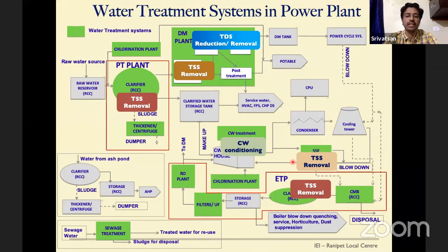Whatever waste is collected in the thermal power plant comes back to the effluent treatment plant, where first it is neutralized, then suspended solids are removed stage-wise. Then there is a TDS reduction. Then this water is reused back in the cooling water cycle. Whatever waste from this thermal power plant remains basically has to be solid waste. You cannot dispose of liquid waste from a thermal power plant as per the recent MOEF norms.